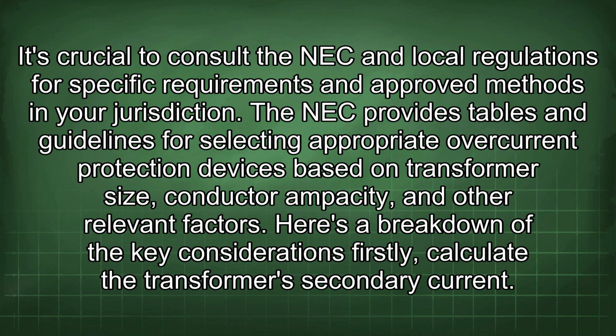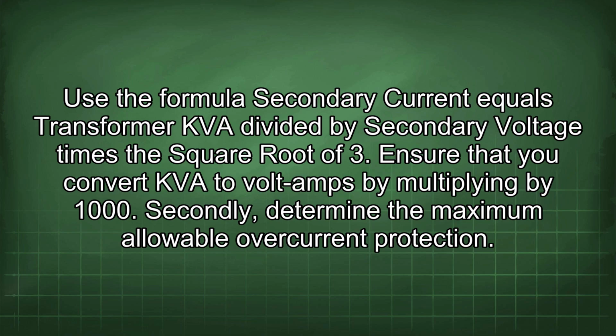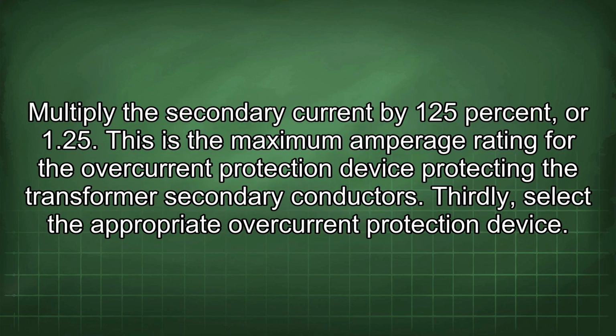The NEC provides tables and guidelines for selecting appropriate overcurrent protection devices based on transformer size, conductor ampacity, and other relevant factors. Here's a breakdown of the key considerations. Firstly, calculate the transformer's secondary current. Use the formula secondary current equals transformer kVA divided by secondary voltage times the square root of 3. Ensure that you convert kVA to volt-amps by multiplying by 1000. Secondly, determine the maximum allowable overcurrent protection. Multiply the secondary current by 125%, or 1.25. This is the maximum amperage rating for the overcurrent protection device protecting the transformer secondary conductors.